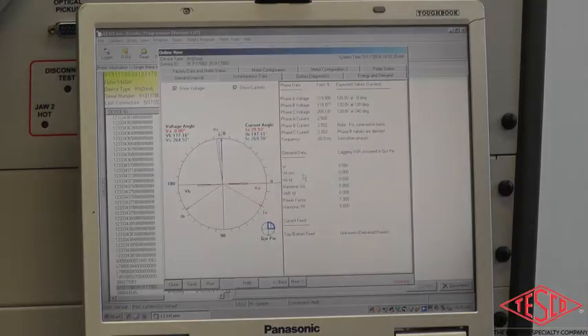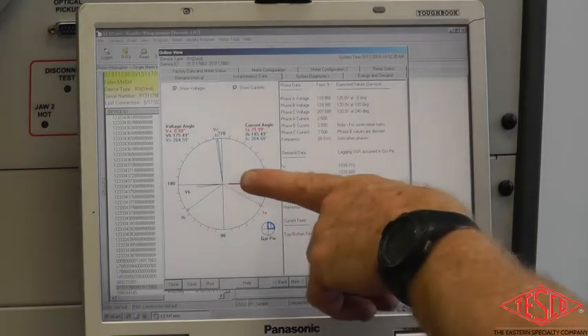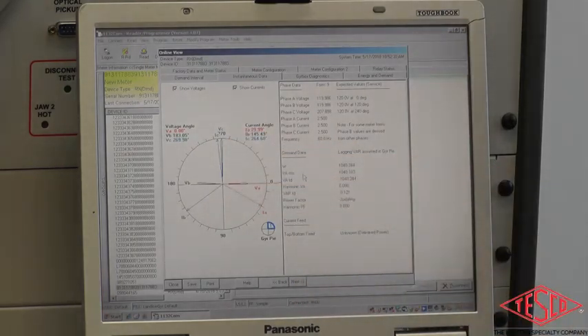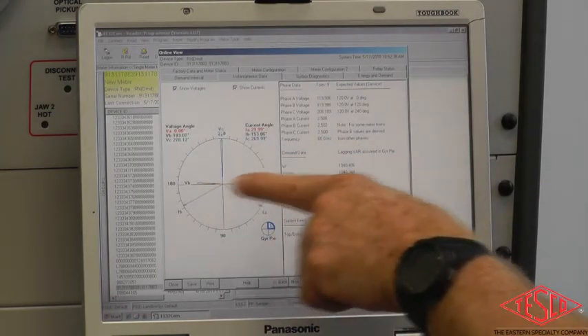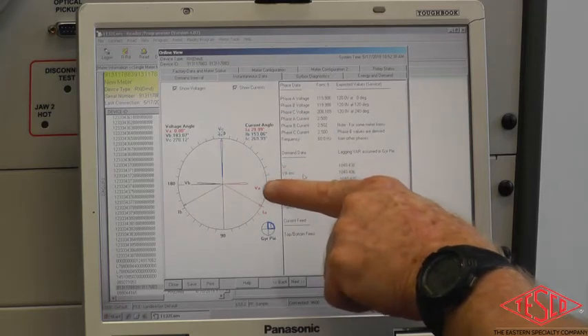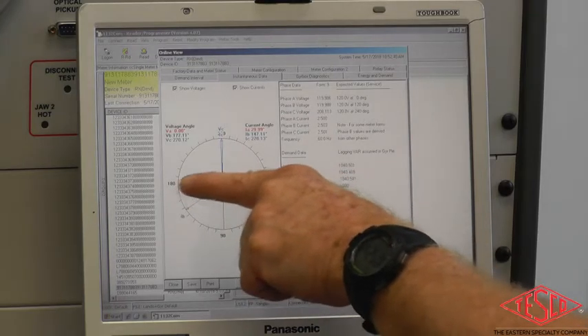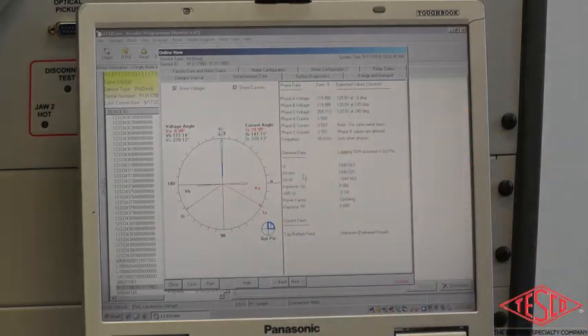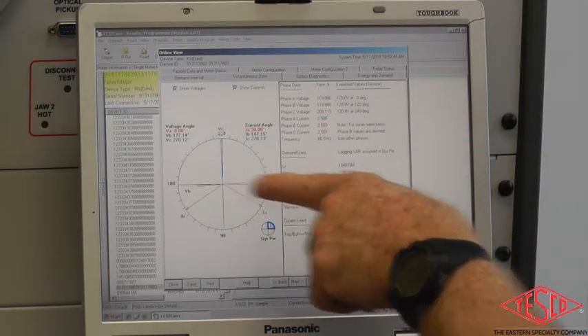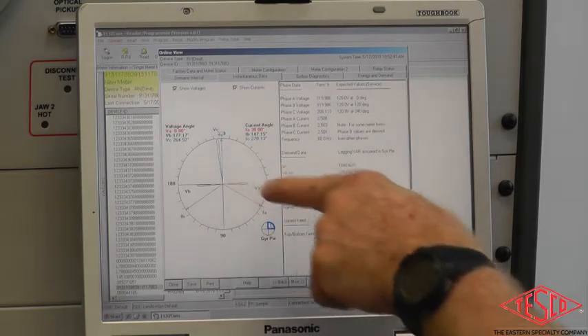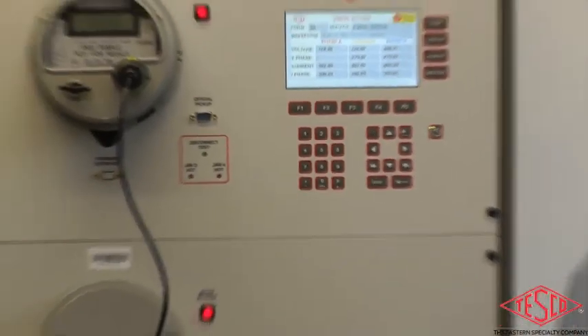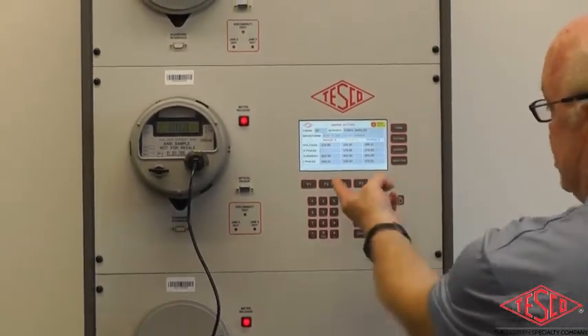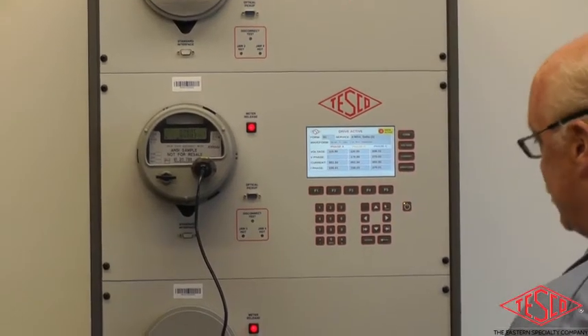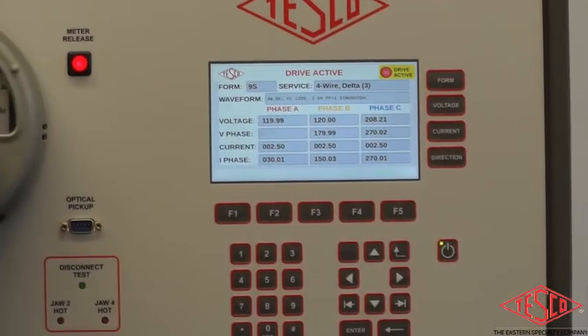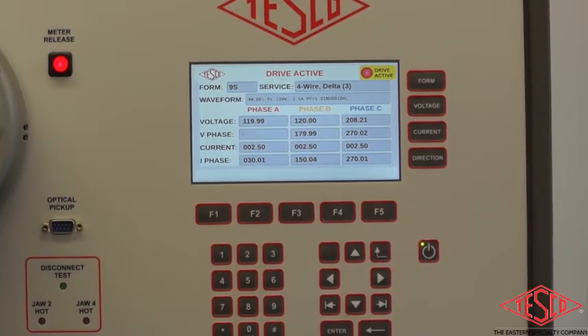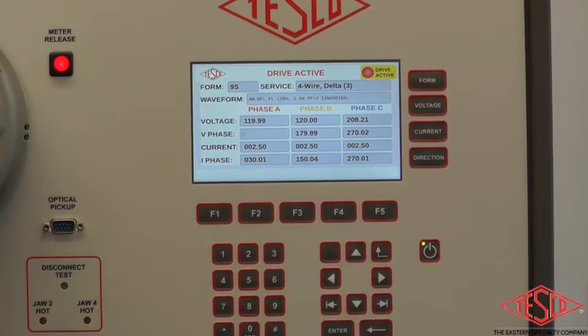Stats, new thing. Now it is updated and you have the vectors of a delta where the voltages are 180 out, A to B, the wild leg, C is this way, and the currents are in a Y configuration. So this actually powers the meter the way it is out on the line, and you can power up all the various services. You can even change your phase angle relationships if you want to get into that. So there's total control of all current, amplitude, and phases via software.